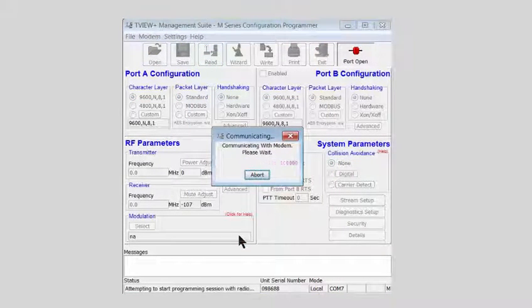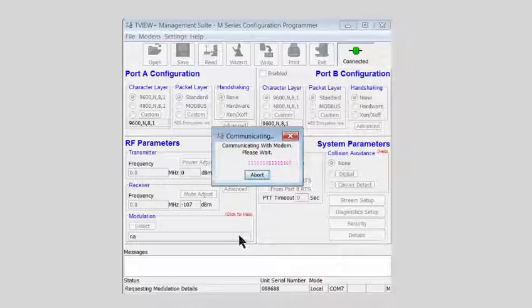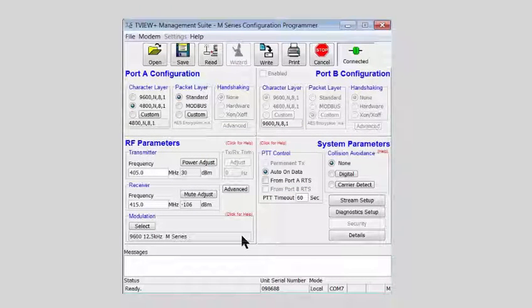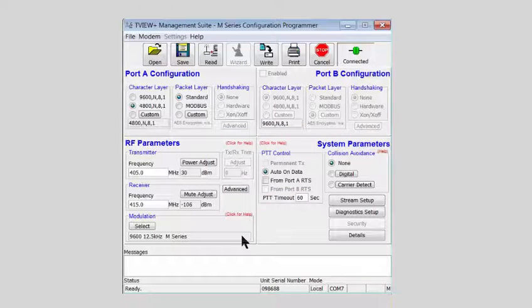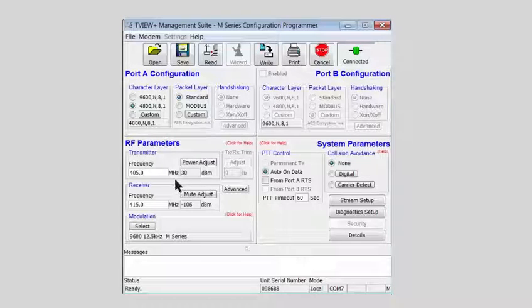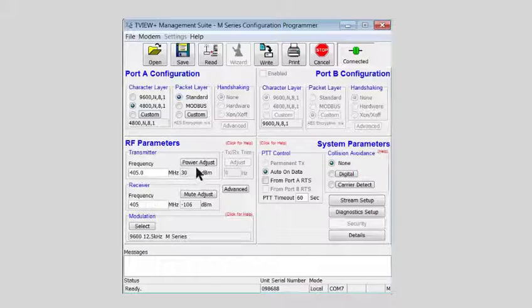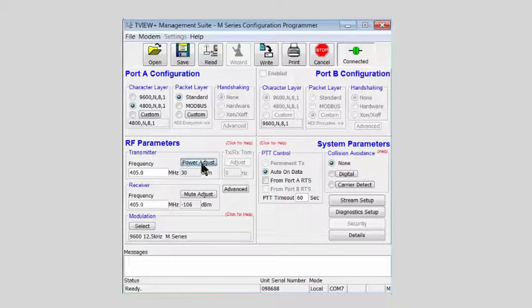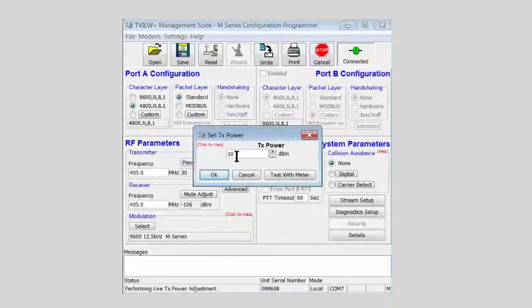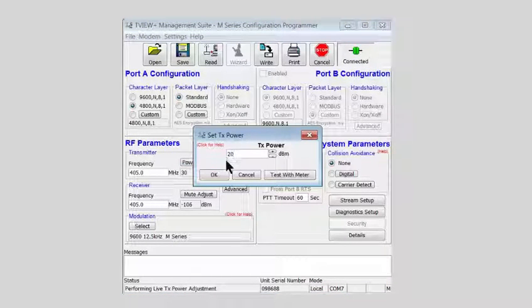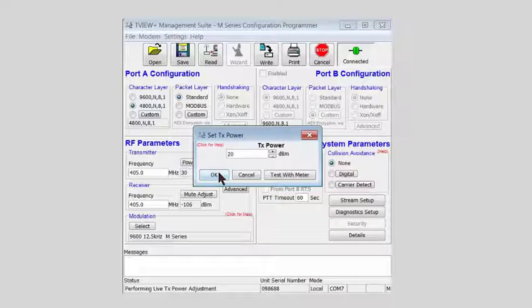The remote radios in a simplex M-Series system are typically configured the same as the entry point radio, with one exception. The transmit and receive frequencies are indeed both going to be the same at 405 MHz, power 20 dBm in this example, 100 mW.